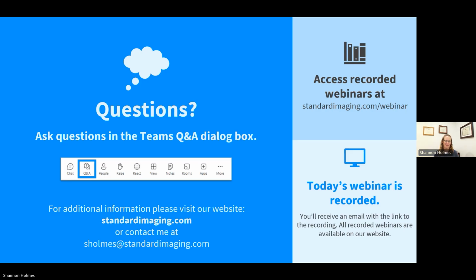Perfect, thank you. Would you recommend a clinic investing in the 4-channel option? That's a good question. I think it really depends on what you're using this for. If you are looking at replacing a check source with a phantom like our constancy check phantom, or if you want the ability to measure more than 2 detectors at a time within one of your QA phantoms, then yes, I would recommend considering the 4-channel. Otherwise, if that's not something that is necessary at your clinic, if that's not something that you see yourself needing, then I would strongly recommend the 2-channel instead of the 4-channel. I think 4 might be overkill for a lot of centers, but it is necessary for some.